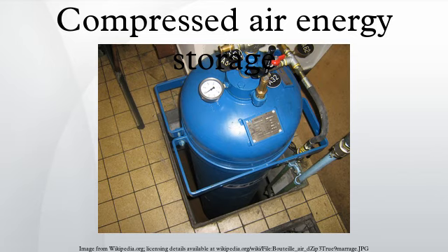The McIntosh, Alabama CAES plant requires 2.5 megajoules of electricity and 1.2 megajoules lower heating value of gas for each megajoule of energy output, corresponding to an energy recovery efficiency of about 27%. A General Electric 7FA2X1 combined cycle plant, one of the most efficient natural gas plants in operation, uses 6.6 megajoules of gas per kWh generated, a 54% thermal efficiency, compared to the McIntosh 6.8 megajoules, at 27% thermal efficiency.